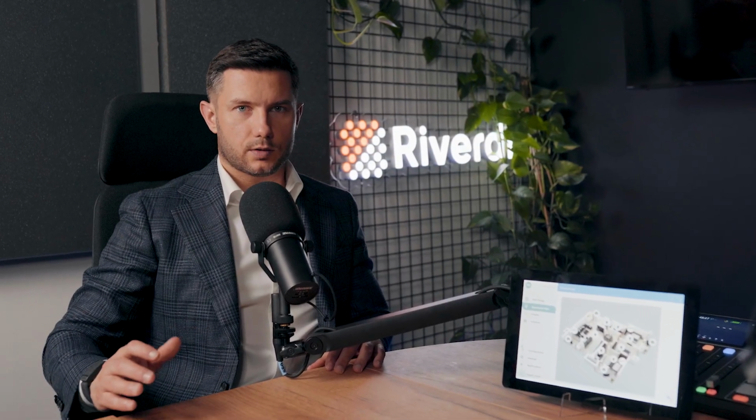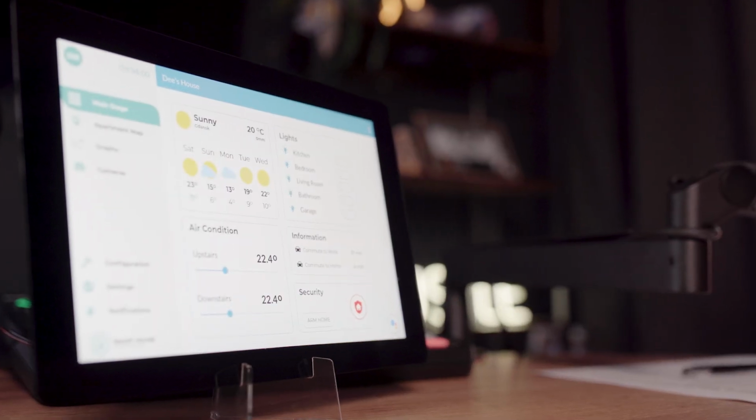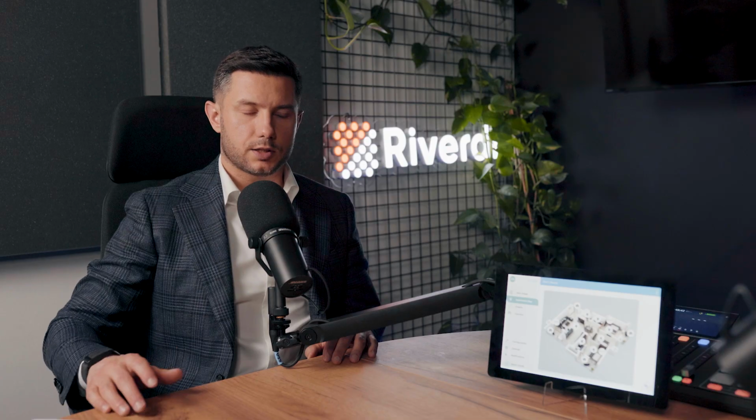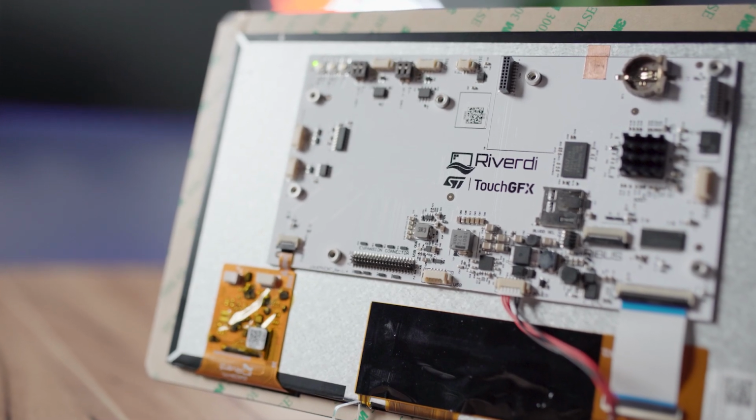Except the touchscreen controller itself, the IC, we are designing our touchscreens with the proper grounding and the FPC that can withstand high immunity tests. And let's jump into the example. We have many customers in the medical field where the requirement is 15 kilovolt of air discharge, electrostatic discharge, and 8 kilovolt of the contact discharge, which is pretty high actually.